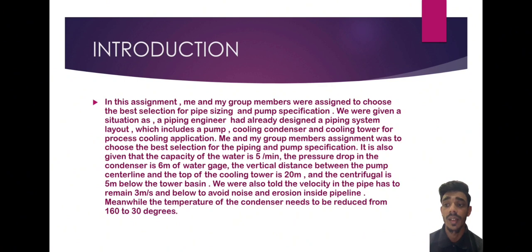It is also given that the capacity of the water is 5 m³ per minute and the pressure drop in the condenser is 6 m of water gauge. The vertical distance between the pump center line and the top of the cooling tower is 20 m, and the centrifugal pump is 5 m below the tower basin. We were also told the velocity in the pipe has to be 3 m/s and below to avoid noise and erosion inside the pipe. Meanwhile, the temperature of the condenser needs to be reduced from 160 to 30 degrees.